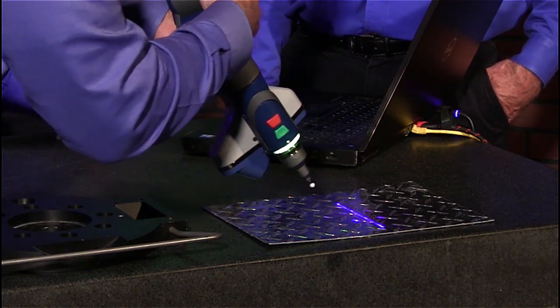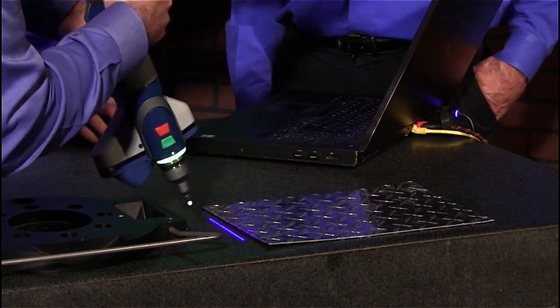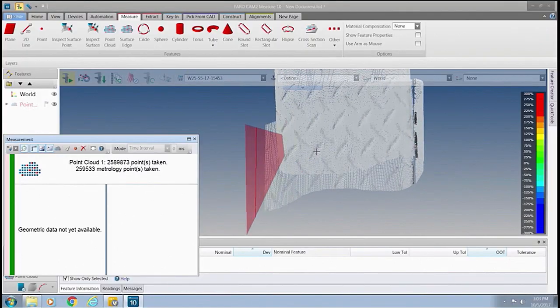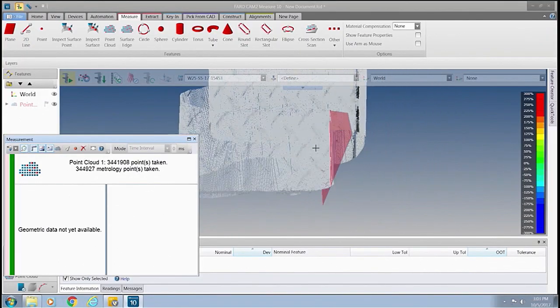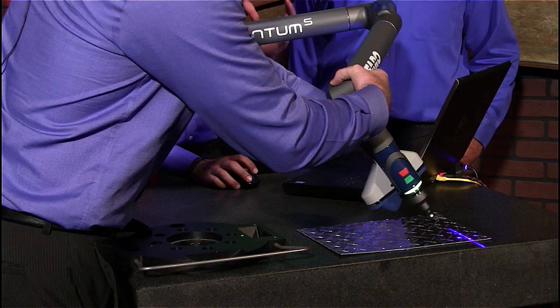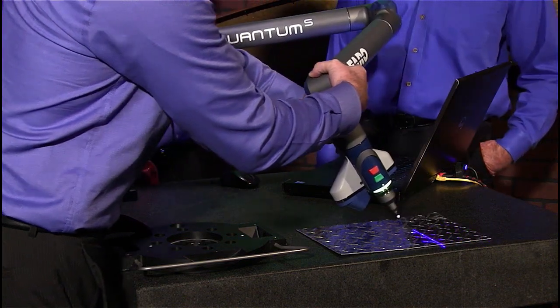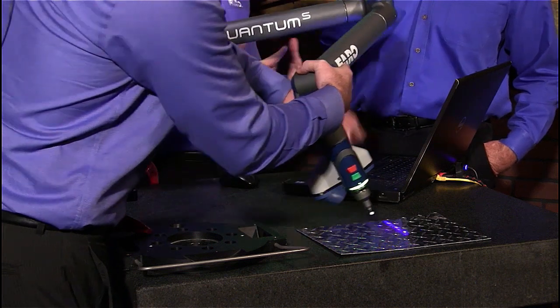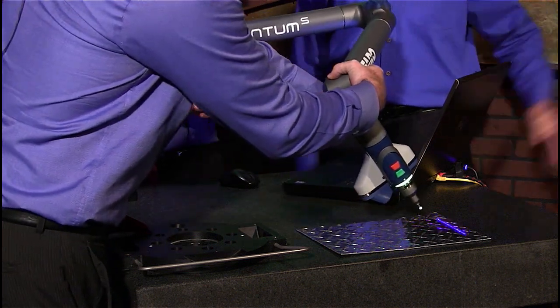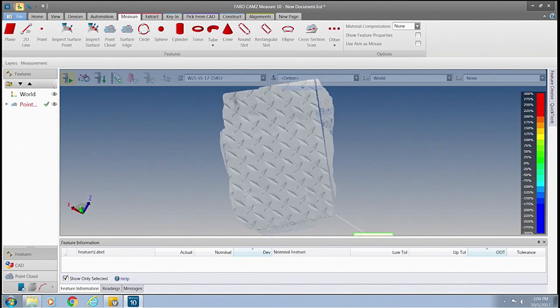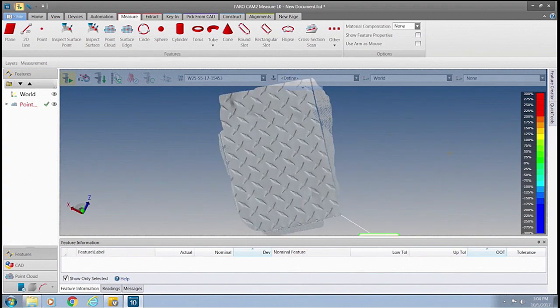Yeah, it looks like you're just scanning as fast as you want. Again, it's capturing a high amount of points very rapidly. And you can always adjust that in case you're doing a large scan. You might want to turn it down if you don't want that amount of data at the computer. 600,000 points a second, you don't need it. And there it is. That's the data we were able to collect. Pretty easy, in real time on a shiny surface, right?